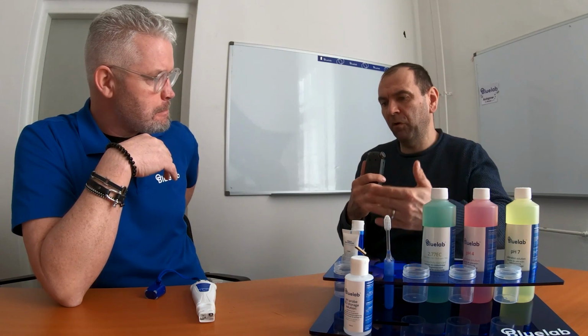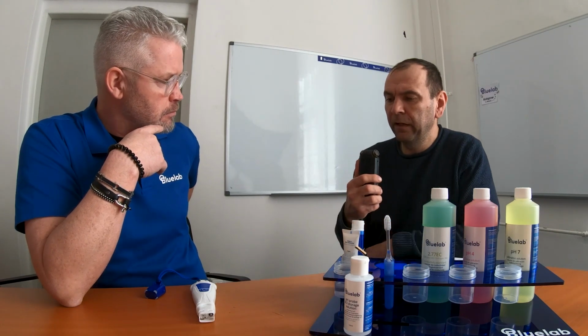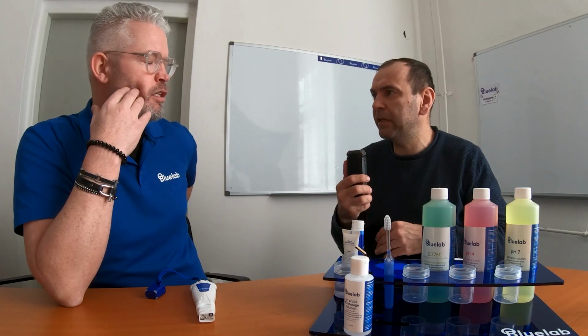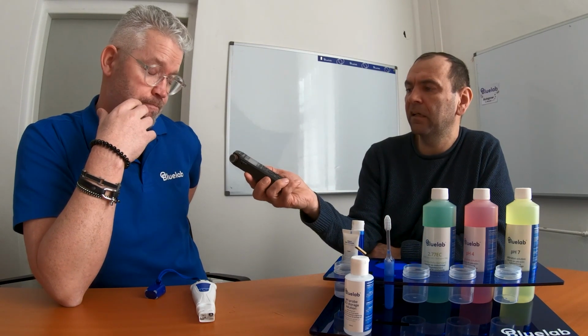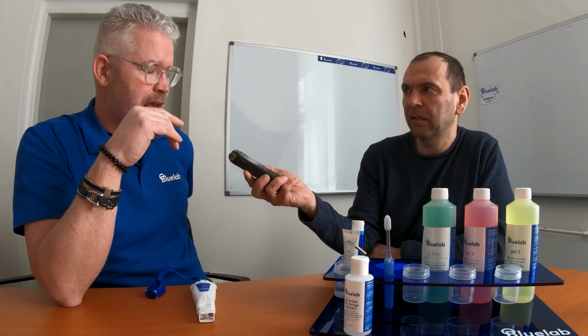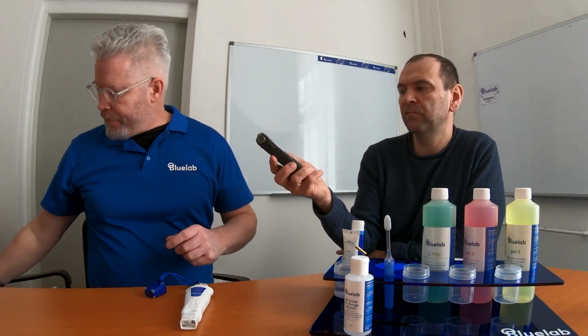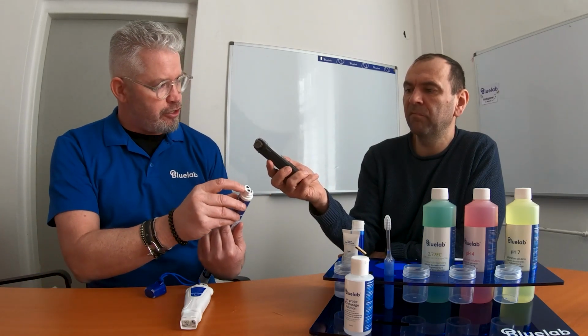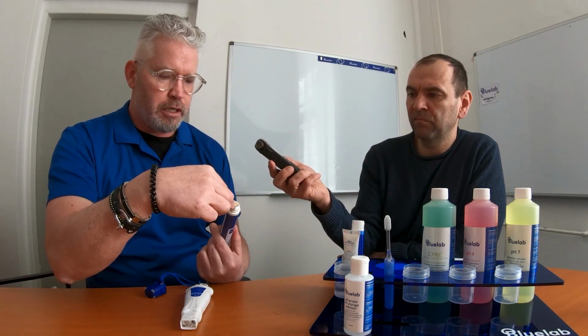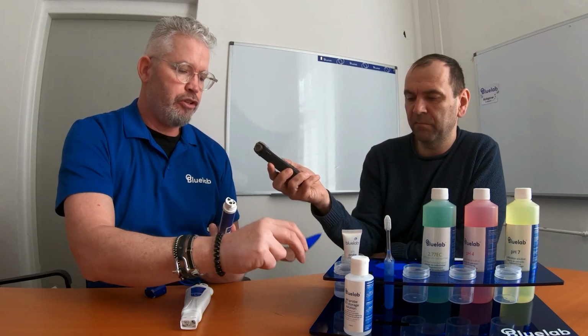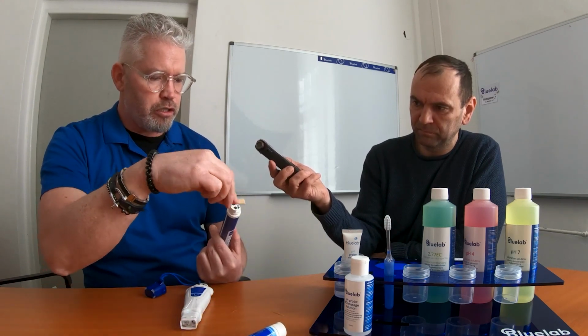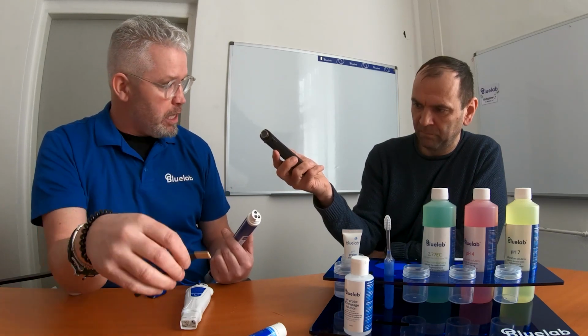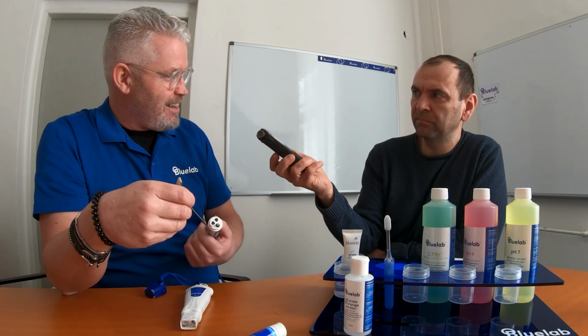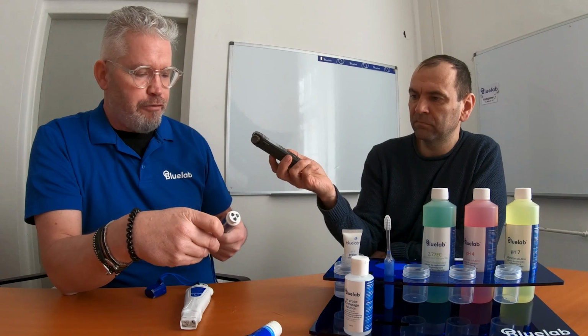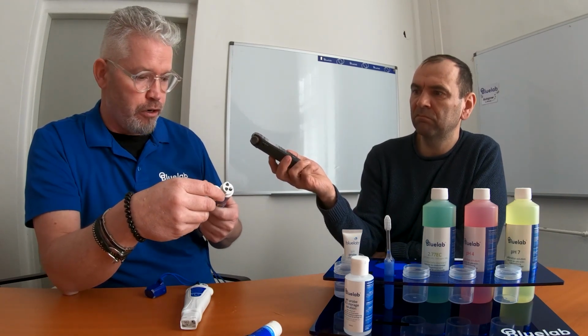Cool. You say that I can prolong the lifespan of a probe. In general, how long can I use it? Because let's say that the EC meter has a longer lifespan than the pH meter, right? Yeah, EC can, as long as you maintain the sensors properly, and that's only, in our case, cleaning. We have, for example, this EC sensor, our truncheon, which has a flat surface. Just clean it. Give it a rub with this one and with some solution we've got here. That's the conductivity probe cleaner. Just a little paste on that with some water, clean it, rinse it. And if you do that, let's say every week as well, you just need to include a maintenance chart for yourself during the week. But if you do that, then you can use this truncheon for many years.